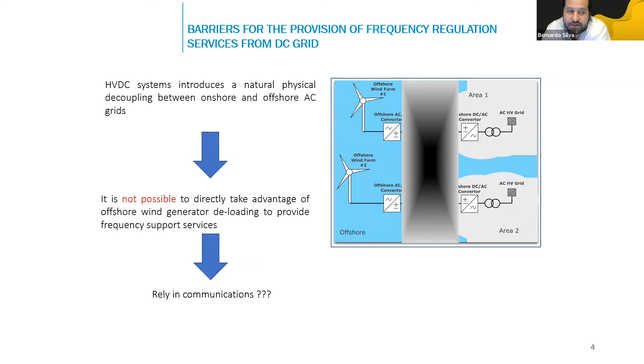It would be very good if offshore farms could do so, because we will not lose as much controllability in the power systems, especially in scenarios where we have a huge deployment and integration of these farms. Nevertheless, the DC grid is a black hole for frequency events and for voltage events. The DC grid decouples all the interconnected areas in terms of frequency and voltage. So the offshore wind farms do not sense frequency deviations, even though the turbines are able to provide frequency support. By using this technology, we are disabling this functionality.